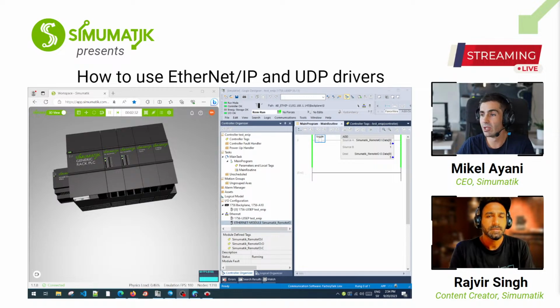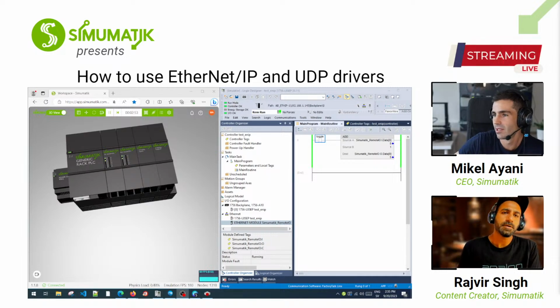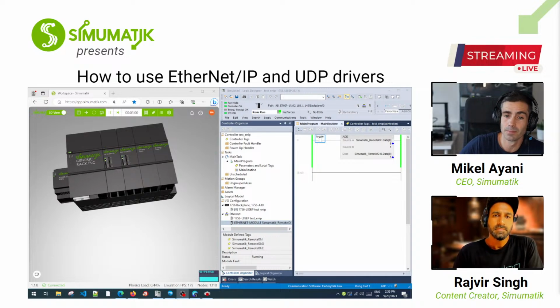Like, I don't know, using S7 protocol, you need to activate the PC interface or put get, and we know that TIA Portal now wants to avoid doing that. Or using OPC UA, you actually open a door to others accessing the memory in your PC and so on. This is the safest way actually to do the virtual commissioning, we could say.